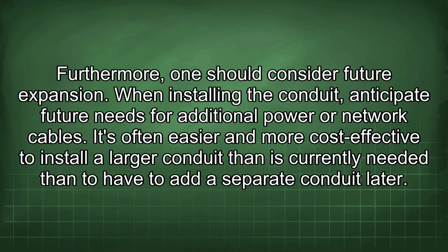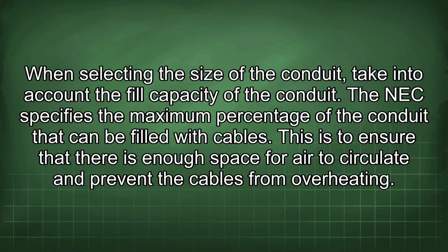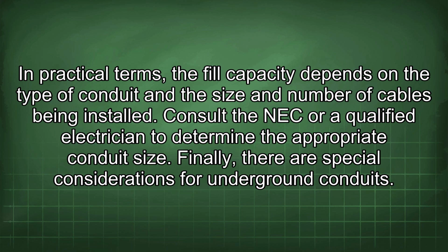Furthermore, one should consider future expansion. When installing the conduit, anticipate future needs for additional power or network cables. It's often easier and more cost-effective to install a larger conduit than is currently needed than to have to add a separate conduit later. When selecting the size of the conduit, take into account the fill capacity of the conduit. The NEC specifies the maximum percentage of the conduit that can be filled with cables. This is to ensure that there is enough space for air to circulate and prevent the cables from overheating. In practical terms, the fill capacity depends on the type of conduit and the size and number of cables being installed. Consult the NEC or a qualified electrician to determine the appropriate conduit size.